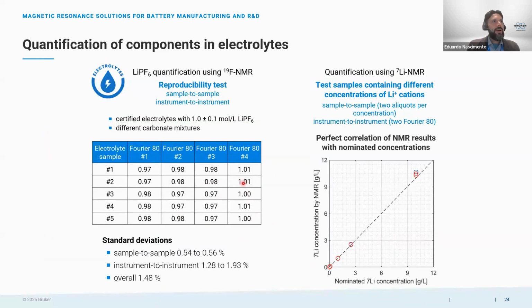So as I said in the beginning, here I am presenting some reproducibility results. If you look in the column, we have here the same sample that was prepared in five different tubes. You can see that for one system, the sample-to-sample variation is quite low, something around 0.5%. The same sample, if you prepare 4 samples and analyze them with 4 different instruments, so now we have instrument-to-instrument variation, which is somewhere around 1.28 to 1.93%. So the overall variation here is estimated at 1.5%. So this is a quite reproducible method.